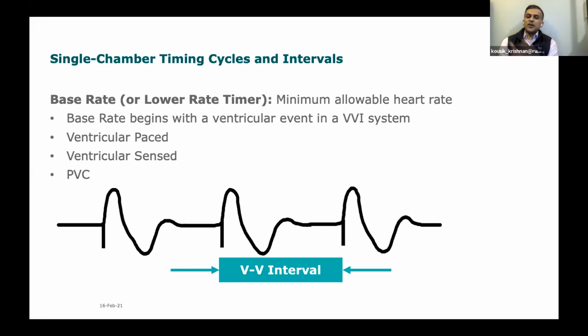So you can understand very simply that after a device paces, it's saying, I cannot let this heart rate get below 60. That means I'm going to look for any intrinsic activity for the next 1,000 milliseconds. If something happens before 1,000 milliseconds, that means the rate is higher than 60 beats per minute, and so it starts another timer, and another timer. If it does not see anything in that 1,000 milliseconds, then that lower rate timer has expired, and it paces. So you will never violate the lower rate limit of 60 beats per minute.